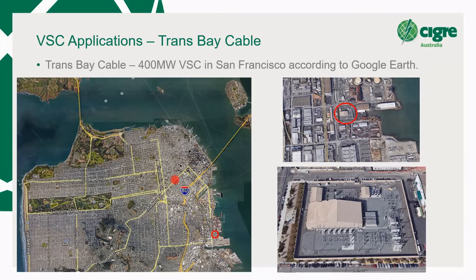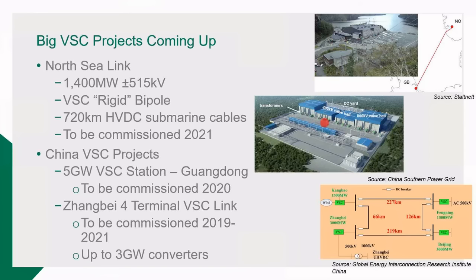That's heavily congested. So what we did was we came along and built a VSC 400 megawatts from up here in the city of Pittsburg, with 80 kilometers of submarine cable into the city. And you can see it's in a very populated area, and that's what the converter looks like. So that's 400 megawatts, relatively small footprint. You can get a sense with the size of the cars, no AC filtering, everything's in a box, and a nice wall around it and beautiful gardens that we put in the front. To the point that I've had friends in San Francisco who live in the vicinity who have never known there's a converter station there. So it's a very good example of an application utilizing that small footprint.